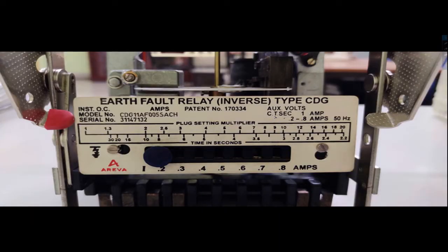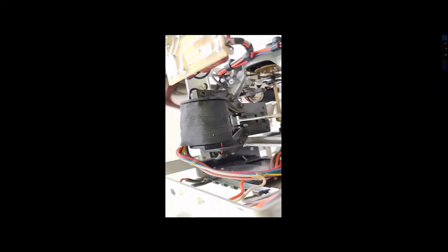Coming to this one, here the auxiliary voltage CT secondary is 1 ampere, so the relay should be connected to a CT whose secondary current is 1 ampere, and the relay can be operated at 0.2 to 0.8 ampere, as I explained here. It's a 50 hertz relay. That table I will explain later. This is the plug setting multiplier versus the operating time of the relay. Using a graph or a picture, we can explain the table later on. So that is called the inverse type CDG relay.